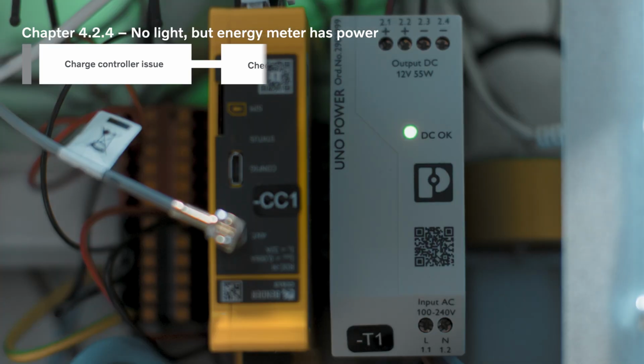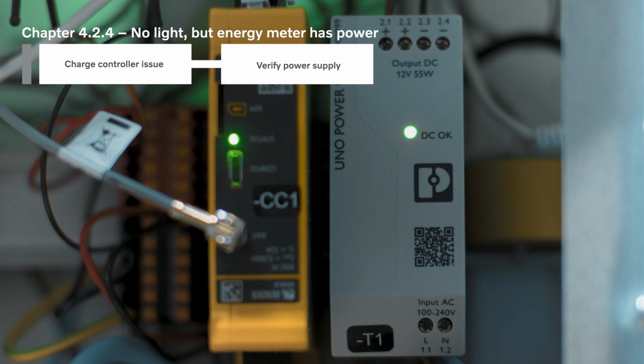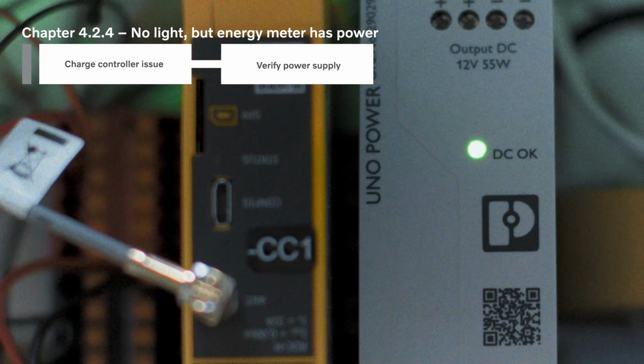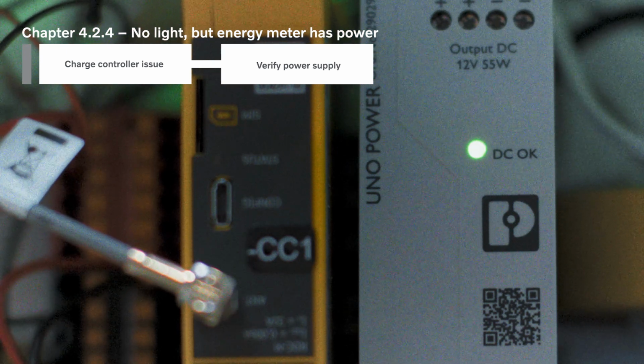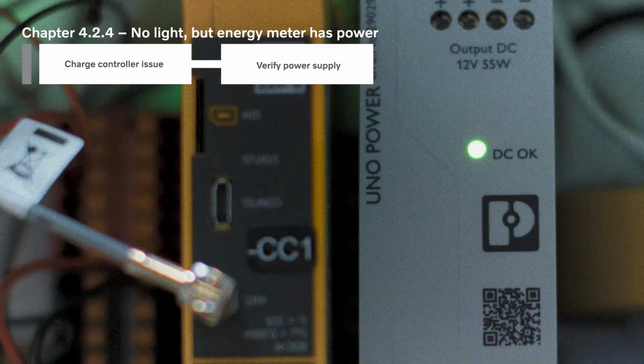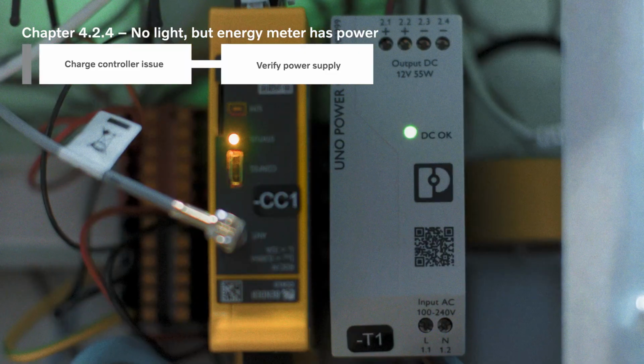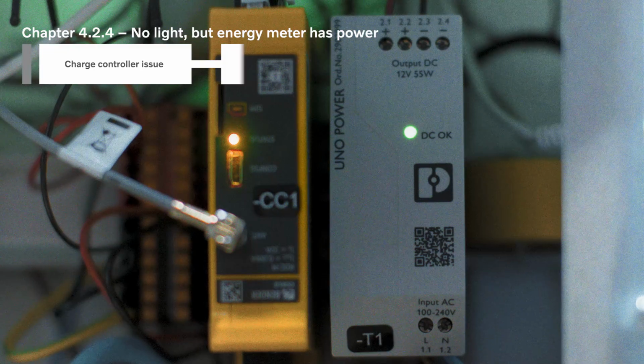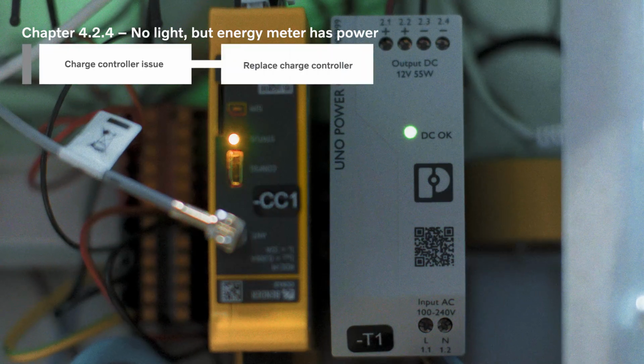If this doesn't solve the problem, verify that the controller has 12-volt DC power supplied via the 4-pole quick connection on the downside of the controller, terminal 1 and 2 from the left, and that the light is blinking green. If the power supply is okay, but the indicator doesn't blink green, then consider replacing the charge controller. If the orange alarm LED indicator on the charge controller is firmly lit, then the charge controller needs to be replaced.